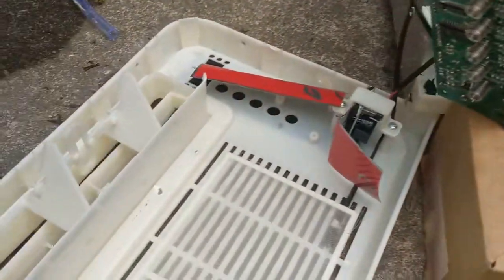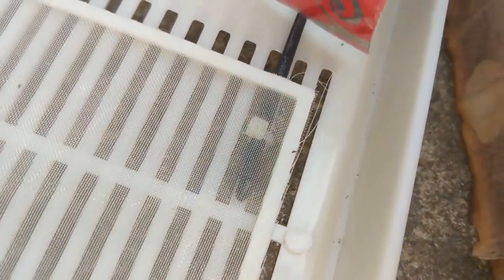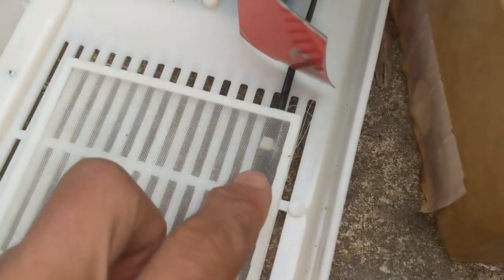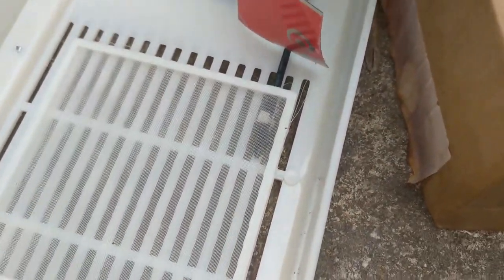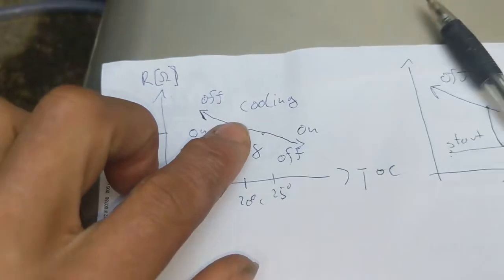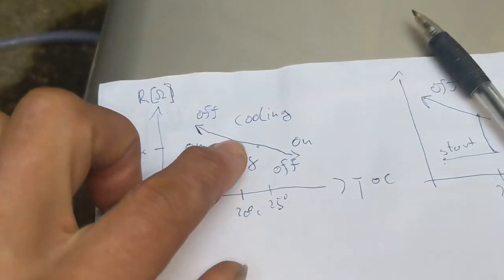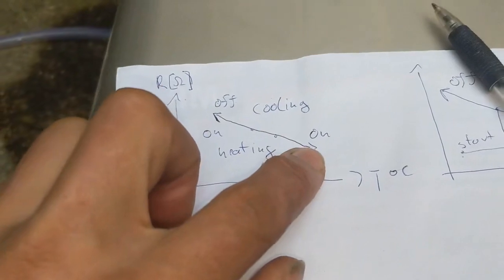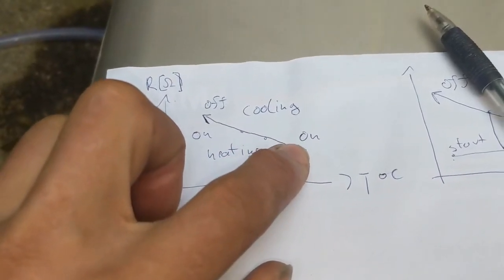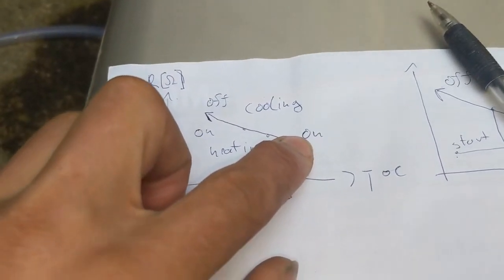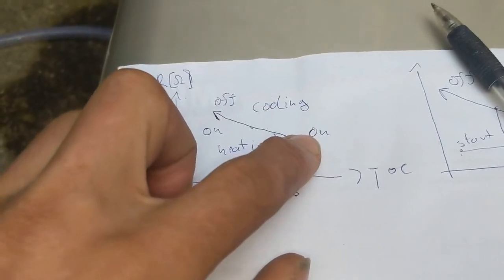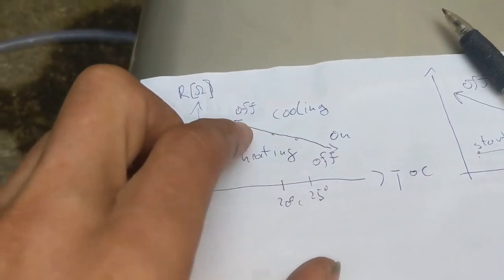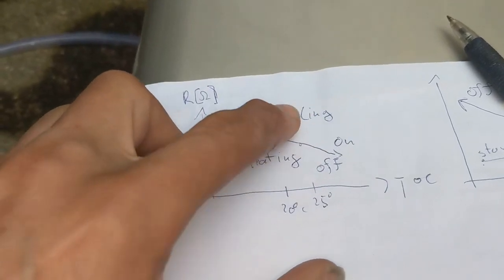I've taken a look at this logic. If you need to switch it, the thermistor here is a 10 kilo ohm thermistor on the upper side. When it gets hot, the resistance decreases and it starts the cooling, the compressor. When the temperature gets colder, the resistance increases and the machine stops.